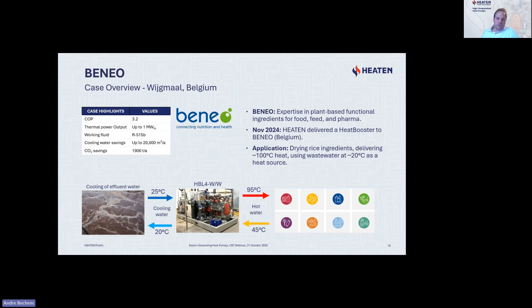We are using an HFO here. The main purpose was not only to save CO2, but also to avoid installing a cooling tower. The customer was also focused on cooling down the temperature of the effluent water, because in Europe you are not allowed to release it at higher temperatures than 25 degrees.